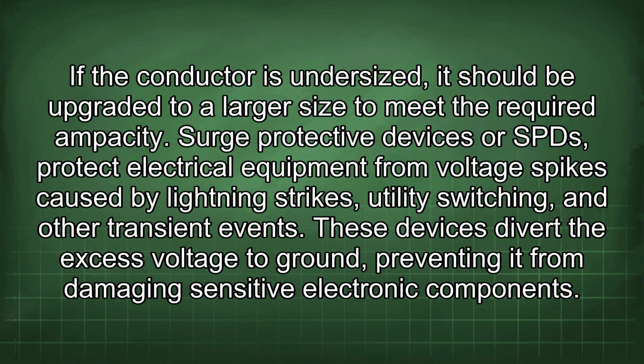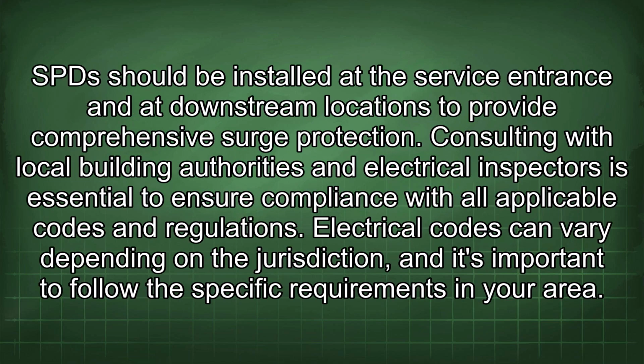Surge protective devices, or SPD, protect electrical equipment from voltage spikes caused by lightning strikes, utility switching, and other transient events. These devices divert the excess voltage to ground, preventing it from damaging sensitive electronic components. SPD should be installed at the service entrance and at downstream locations to provide comprehensive surge protection.